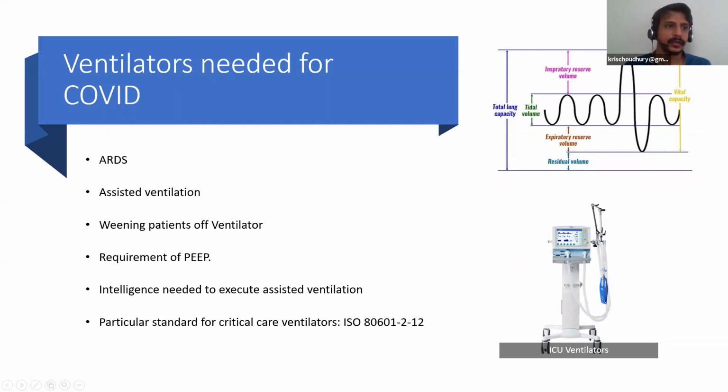When you buy that simulator and test all your modes on it, and ensure that across all lung compliances and all lung conditions the ventilator is behaving properly and acceptably, only then can you sell this ventilator in the market. So without a lung simulator, even if a doctor is testing this untested ventilator on a patient, it is basically unethical. You should not be doing it.